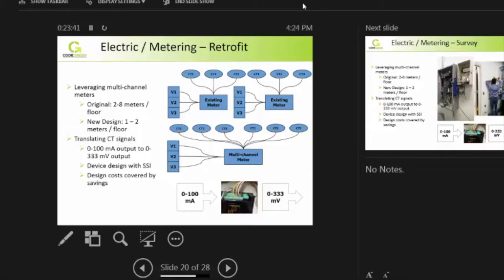This is the idea of using a single voltage connection to feed multiple loads. We used Dent Instruments PowerScout 24, which can measure up to 8 three-phase loads with one electric room on each floor at this building.